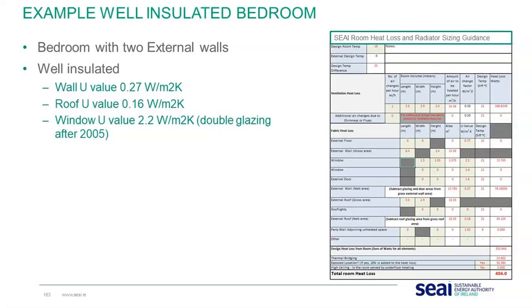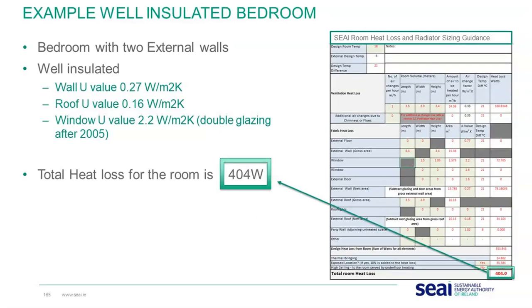Whereas in a well-insulated room, and this is quite common because what can happen in parallel with the installation of a heat pump, homeowners may be doing thermal upgrades to their homes or fabric upgrades. So in this case, the walls have been upgraded, the roof has been upgraded, and the windows have been upgraded. And now when we enter in these calculations, we can see it here. The heat loss for the room has been significantly reduced. It's 2/3 of what it originally was, and it's only 404 watts now. So the example that we looked at, the output of the rad, was 412 watts.